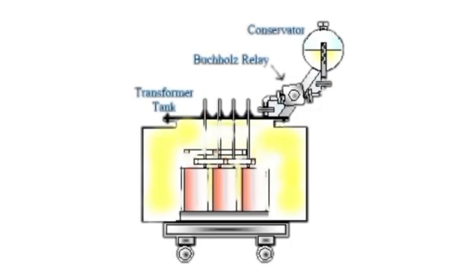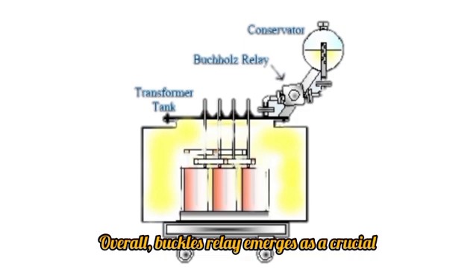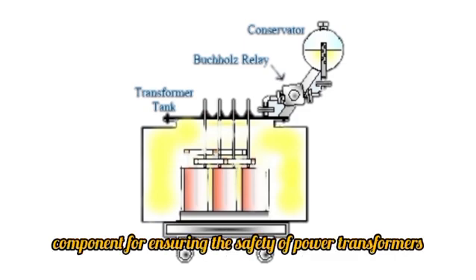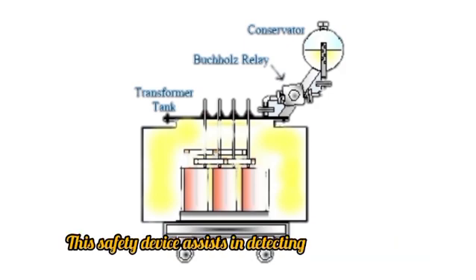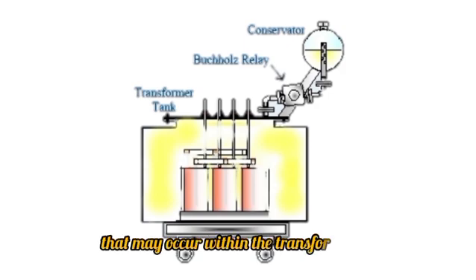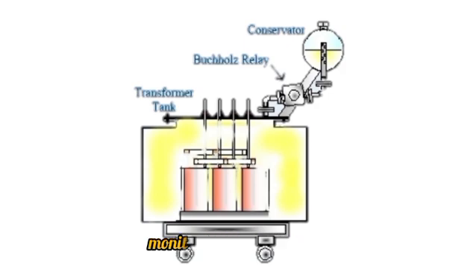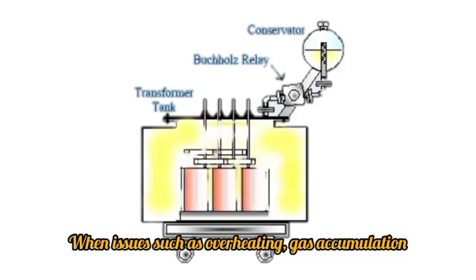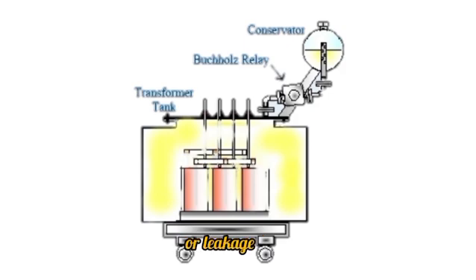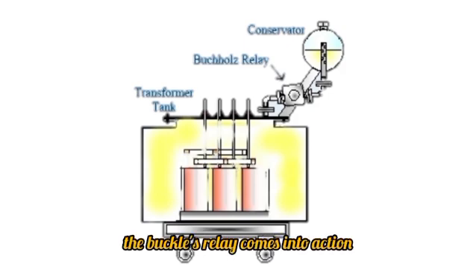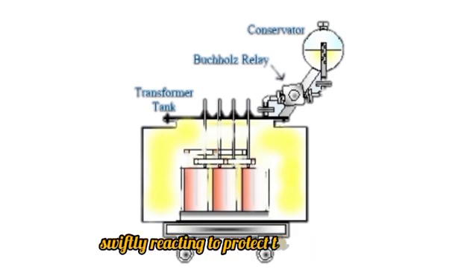Conclusion. Overall, the Buchholz relay emerges as a crucial component for ensuring the safety of power transformers. This safety device assists in detecting potential faults that may occur within the transformer by monitoring the levels of gas and liquid inside. When issues such as overheating, gas accumulation, or leakage arise, the Buchholz relay comes into action, swiftly reacting to protect the transformer.